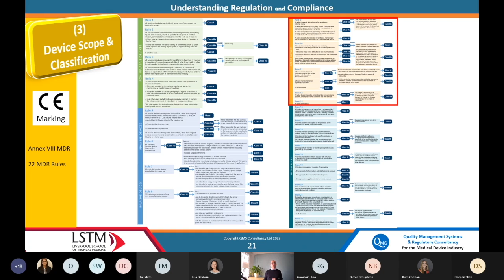Now, in the past, under the Medical Device Directive, software was only discussed 7 times in total throughout the whole of the directive. And the only rule you could pin software to was Rule 10. And what Rule 10 said is highlighted in yellow, and it says active devices intended for diagnosis are in Class 2A. So that meant that any software that didn't do diagnosis was Class 1 by default against Rule 12 of the MDD. The MDR, which is the orange text, now under Rule 10, it says active devices intended for diagnosis and monitoring. So if you've got some software and it does monitoring, then the minimum it's going to be is a Class 2A device.